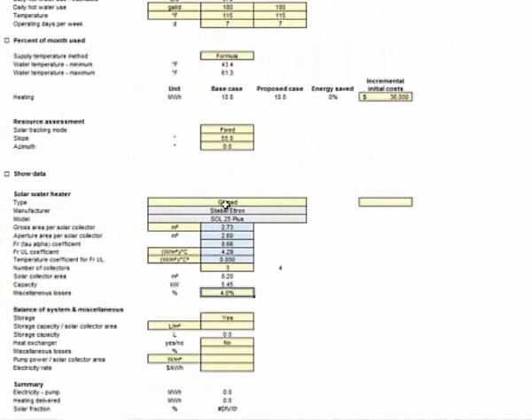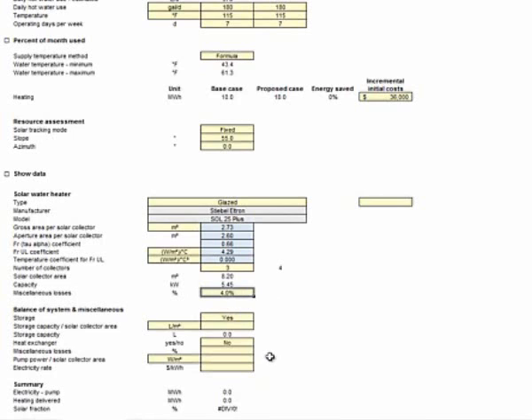So if I'm facing due south, which is right here, and I have absolutely no trees, no shading effect, then I could probably just do a total percentage of about 4%. Now, let's say I have a total net shading over these thermal modules and we're looking at somewhere near 10-15% of shading. Then I'm going to want to include that right here. I'm going to want to make this, say, then 14 to 10% of shading plus the 4% of miscellaneous loss.